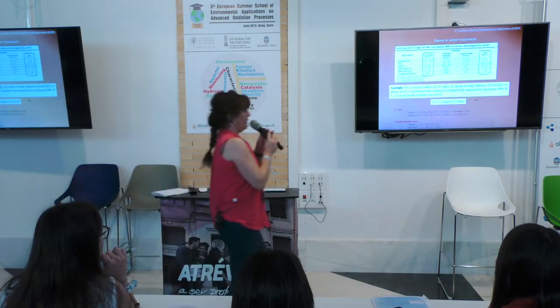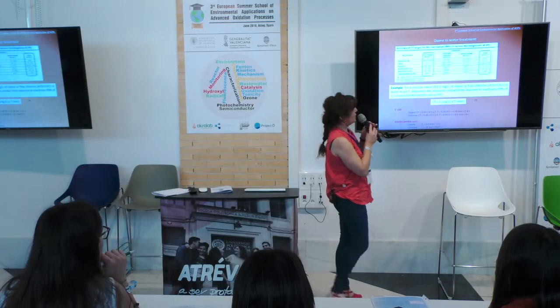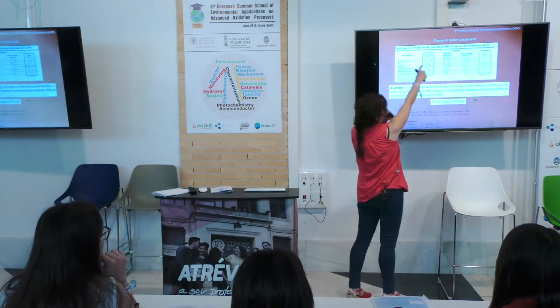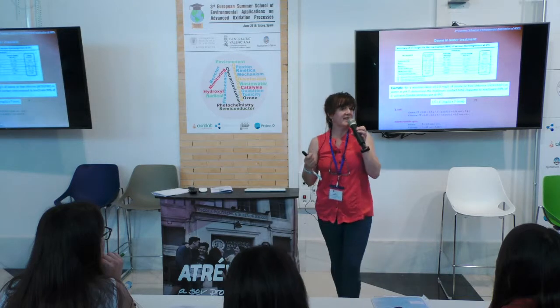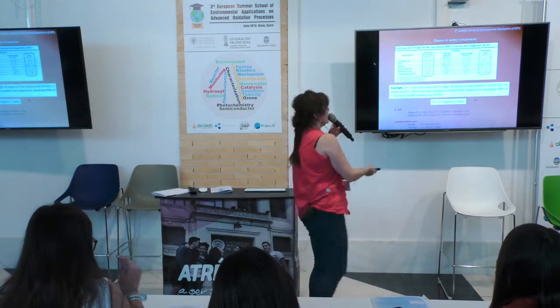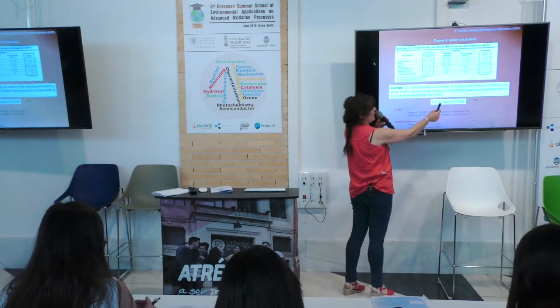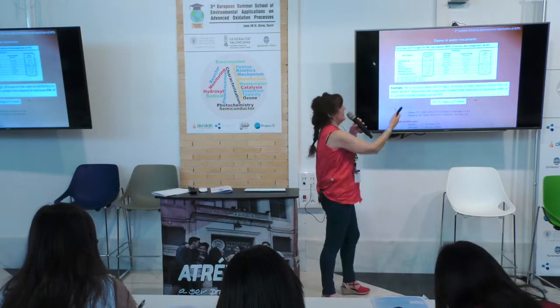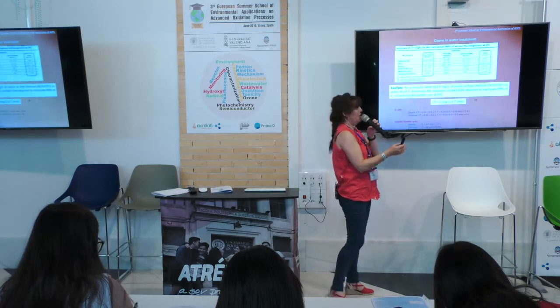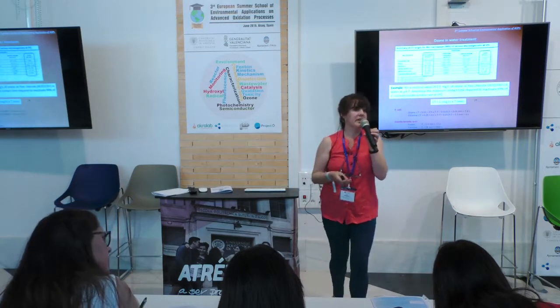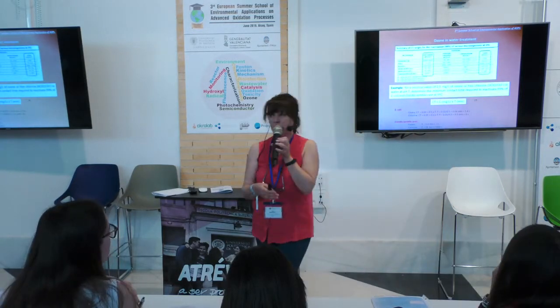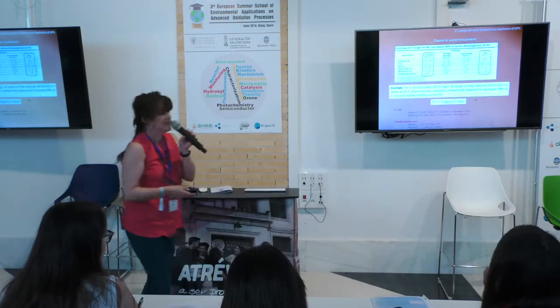In the case of ozone, for E. coli, we look for E. coli with ozone, 0.02 the CT. Since our residual concentration is set to be 0.5, we obtain that the contact time in seconds will be 2.4. Doing the same for chlorine, it will be 6 seconds.